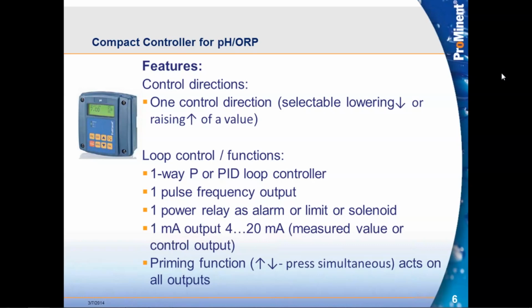So we are able to use maybe other pumps as well that can take a pulsing signal in, or if we're controlling the pump with that milliamp signal, the 20 milliamps, it would ramp to 20 milliamps by pressing the up and down arrows simultaneously. So it's a nice way to help prime the pump, even if the pump doesn't necessarily have a prime function available.